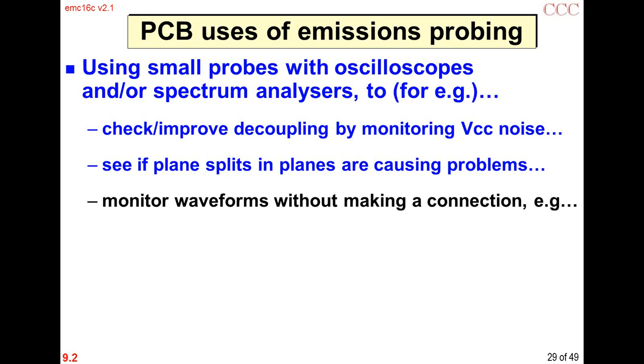To monitor waveforms without making a connection, in the example of a plane, you might tape a probe near the open end of the split and pick up the noise from the split. Then, while exercising the equipment, see if shorting the split out or linking it with capacitors gets rid of the noise without affecting operation. You can monitor waveforms without making a connection.